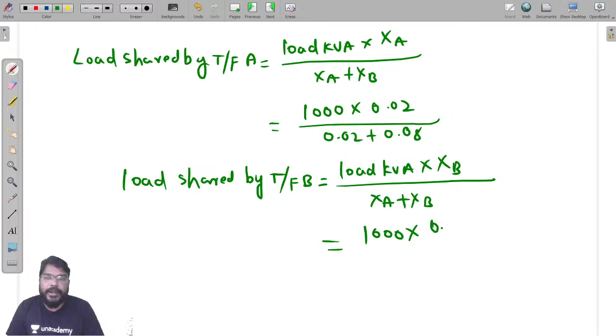Calculate and you will get the answer for load shared by transformer B. The formula here is load kVA into XB divided by XA plus XB. Load kVA is 1000, into XB which is 0.08, divided by XA plus XB, that is 0.02 plus 0.08.